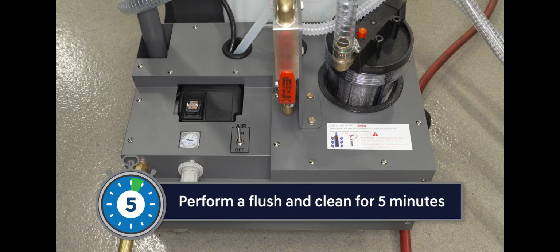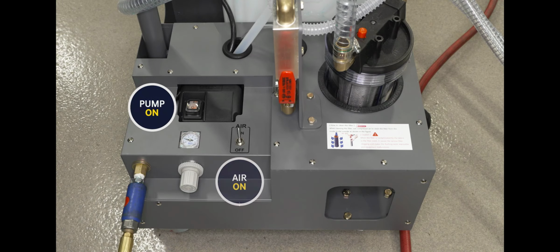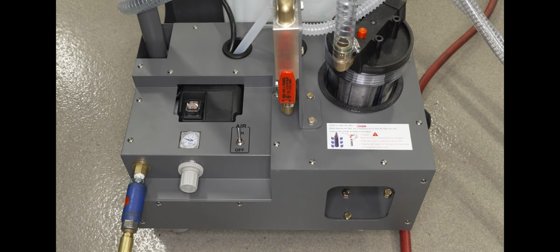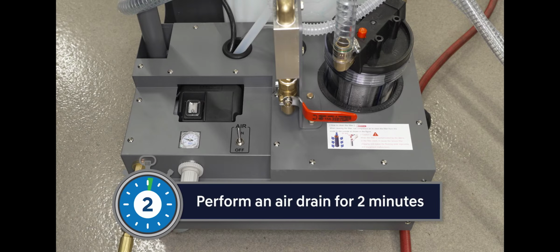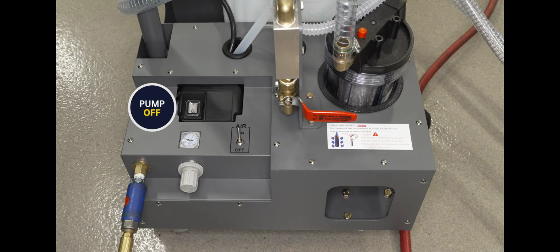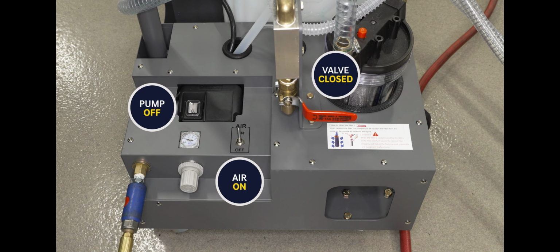Perform a coolant flush and filter clean for 5 minutes by turning the pump on, turning the air supply switch on, and opening the inlet valve. After 5 minutes, perform an air drain for 2 minutes. Turn the pump off, leave the air supply switch on, and close the inlet valve.